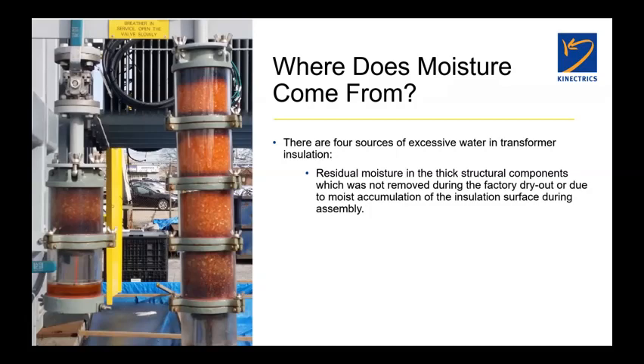And I want to emphasize it's not that the transformer OEM is doing anything nefarious or untoward. As mentioned, cellulose is simply so hydrophilic, it is impossible to remove all the water from the paper. And so there is always some moisture that comes along for the ride when you get a new unit. Ideally, it should be somewhere in the range of about 0.3% by weight. Depending on the drying process that the factory uses, and they all do different things, it could be higher. It could be north of 0.5%. And factories that do not use vapor phase drying systems tend to struggle a little bit more than those that do. So not all are equal in that regard.